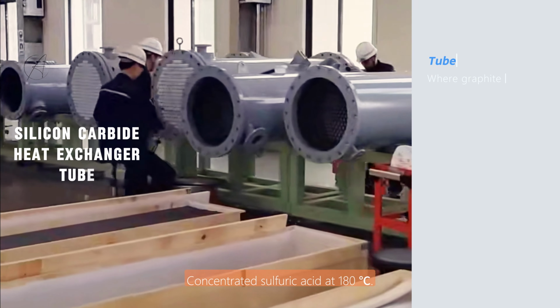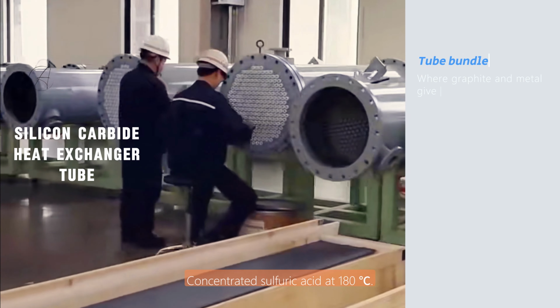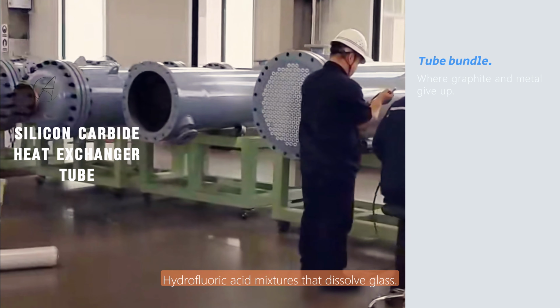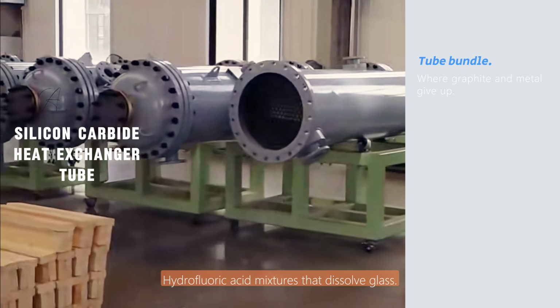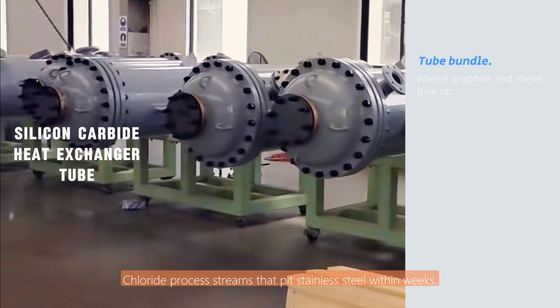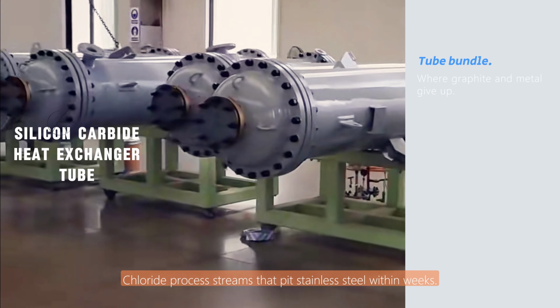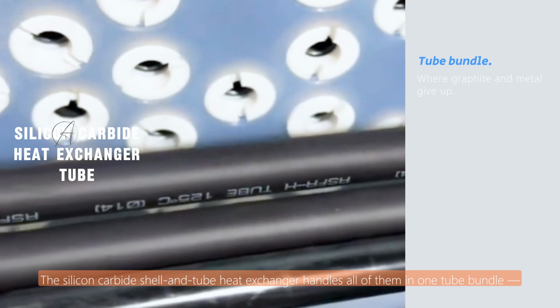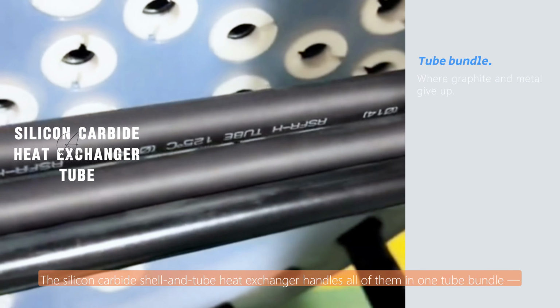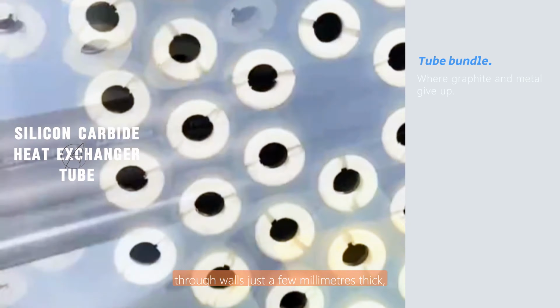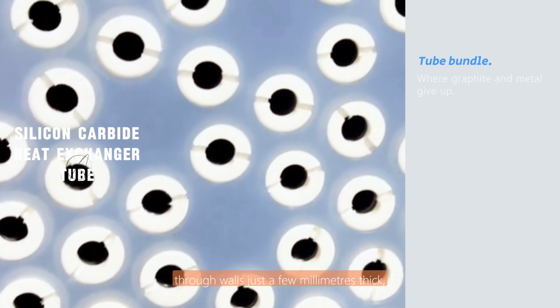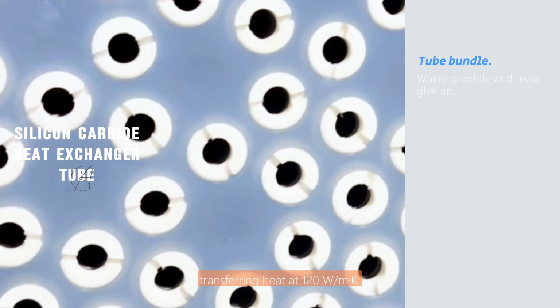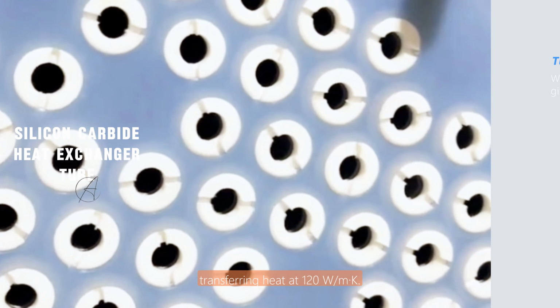Concentrated sulfuric acid at 180 degrees Celsius, hydrofluoric acid mixtures that dissolve glass, chloride process streams that pit stainless steel within weeks. The silicon carbide shell and tube heat exchanger handles all of them in one tube bundle, through walls just a few millimeters thick, transferring heat at 120 watts per meter per Kelvin.